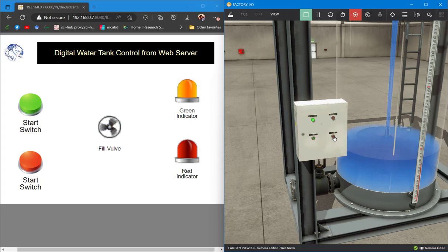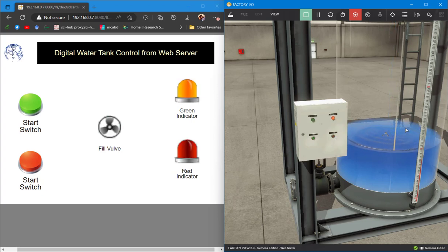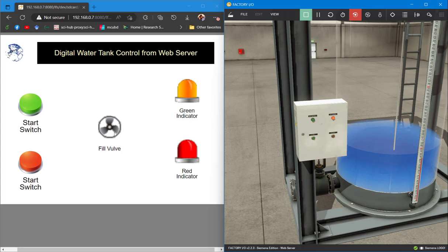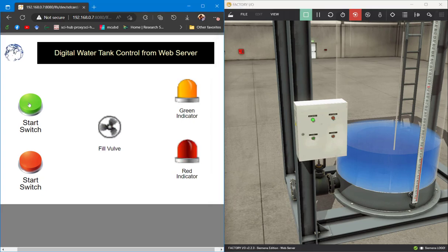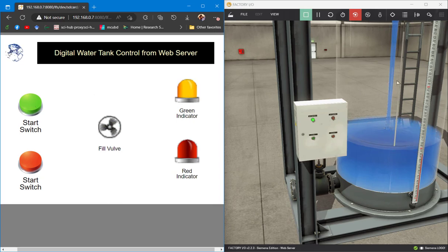Now when we press the stop button, the fill valve has stopped and the red indicator is moving. Both in the electrical panel as well as the web server, the fill valve has stopped. Using the web server green start switch and stop switch, we can also control the whole setup.